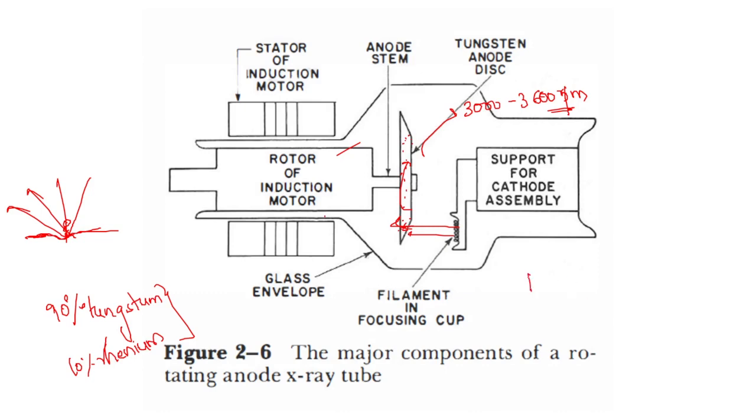Today there are X-ray machines with anodes rotating at around 10,000 rotations per minute. So increased velocity, making the anode stem as short as possible, and also decreasing the inertia of the anode, all these have made the anode assembly work properly.